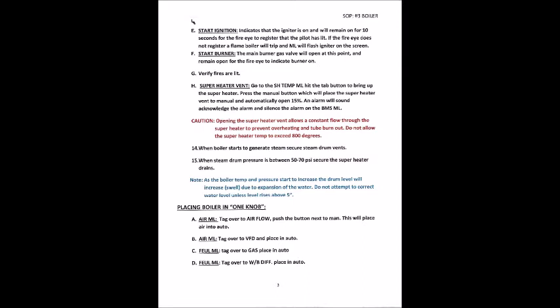Caution: opening the superheater vent allows a constant flow through the superheater to prevent overheating and tube burnout. Do not allow the superheater temp to exceed 800 degrees. 14. When boiler starts to generate steam, secure steam drum vents. 15. When steam drum pressure is between 50 to 70 psi, secure the superheater drains. Note: as the boiler temp and pressure start to increase, the drum level will increase as well due to expansion of the water. Do not attempt to correct water unless level rises above 5 inches.